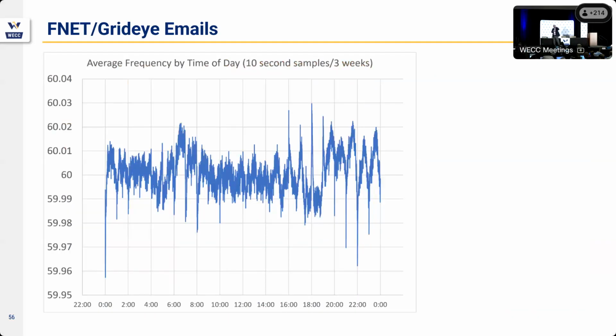So we started getting all these FNet emails, and everybody goes, what's going on at the top of the hour? This is an average frequency by time of day, 10-second samples for 3 weeks this summer, and if you notice, there's a whole bunch of frequency spikes right on the top of the hours. We believe this is EV charging in California driving these spikes. One of the basics of our grid operations is that loss of resource, increase of load, is random and not coordinated. With the Internet of Things, that is no longer the case.